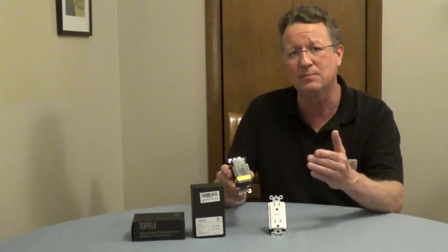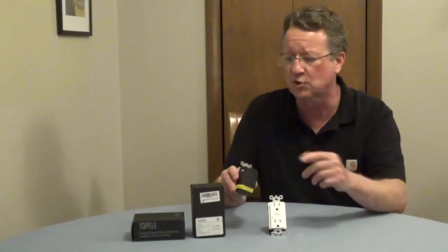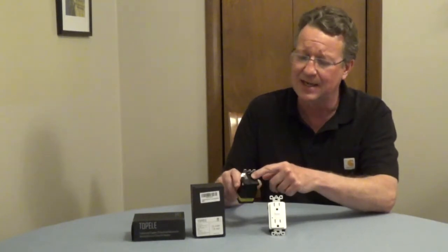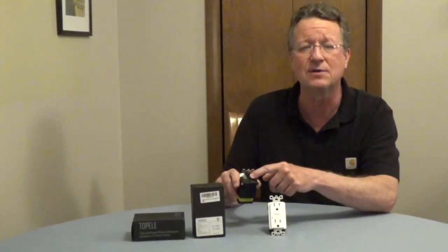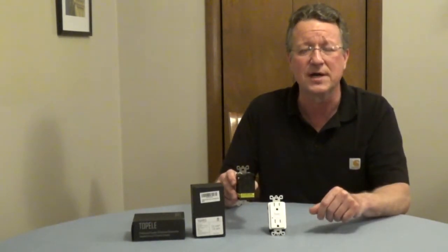If you have one cable, you're going to be connecting the hot black wire to the brass side, the white neutral wire to the silver side, and your ground wire to the green grounding screw. If you're in an area that uses conduit, you may not have a ground wire.